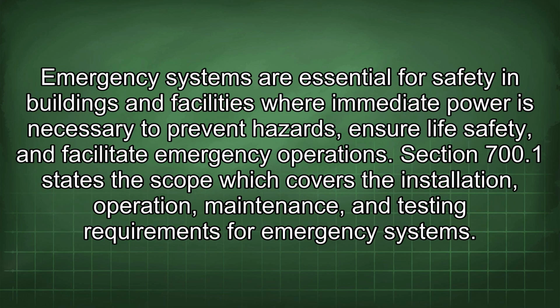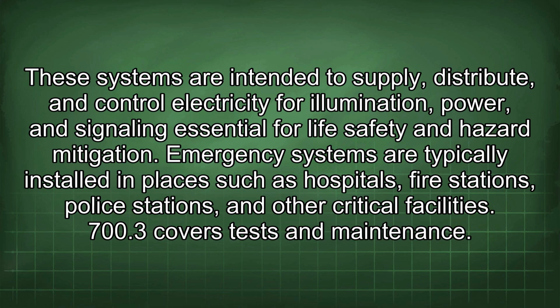Emergency systems are essential for safety in buildings and facilities where immediate power is necessary to prevent hazards, ensure life safety, and facilitate emergency operations. Section 700.1 states the scope, which covers the installation, operation, maintenance, and testing requirements for emergency systems. These systems are intended to supply, distribute, and control electricity for illumination, power, and signaling essential for life safety and hazard mitigation. Emergency systems are typically installed in places such as hospitals, fire stations, police stations, and other critical facilities.